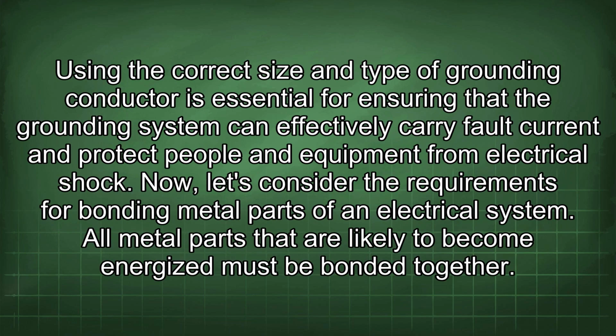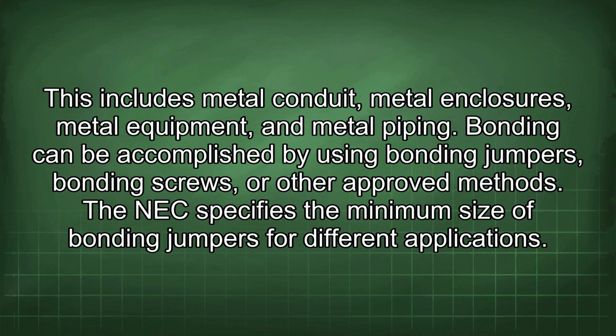Using the correct size and type of grounding conductor is essential for ensuring that the grounding system can effectively carry fault current and protect people and equipment from electrical shock. Now let's consider the requirements for bonding metal parts of an electrical system. All metal parts that are likely to become energized must be bonded together. This includes metal conduit, metal enclosures, metal equipment, and metal piping. Bonding can be accomplished by using bonding jumpers, bonding screws, or other approved methods. The NEC specifies the minimum size of bonding jumpers for different applications.